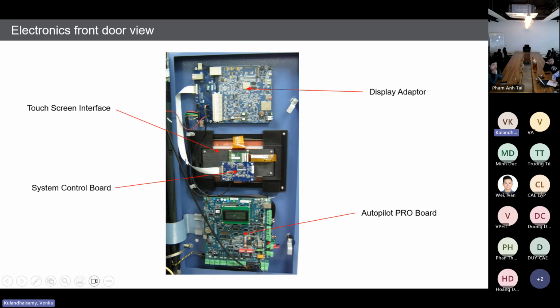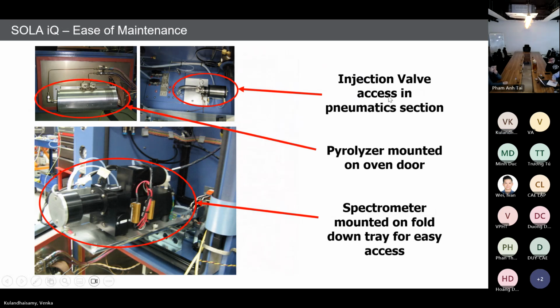Okay. So this is the electronic chamber main panel. The panel consists of 3 main items. One is the display adapter with the PCB, then the touch screen board and assembly, then the autopilot pro board. This is called the CPU board. This CPU board controls all the electronic circuits. So the injection valve is accessed in the pneumatic section, the pyrolyzer is mounted on the oven door, and the spectrometer is mounted on a foldable tray. So whenever you want to do maintenance, it's very easy compared with SOLA 2.